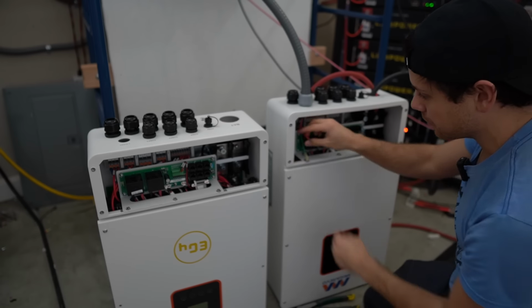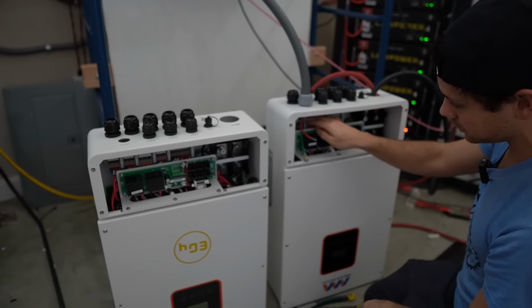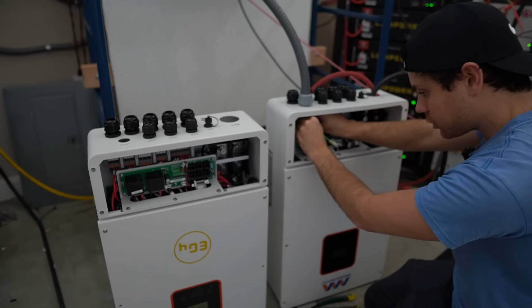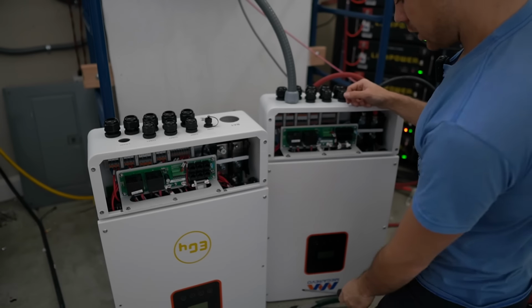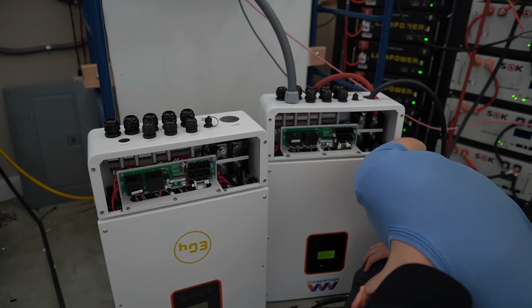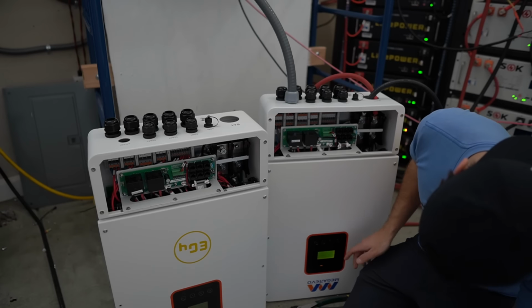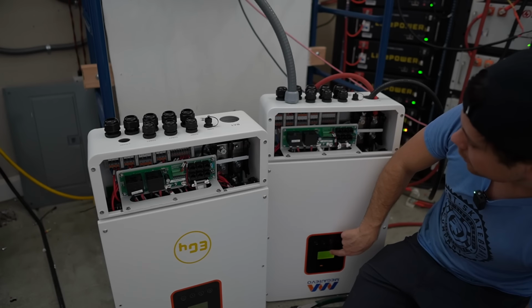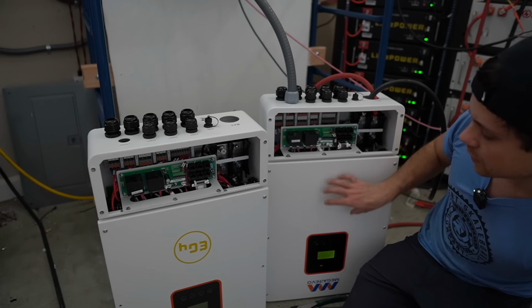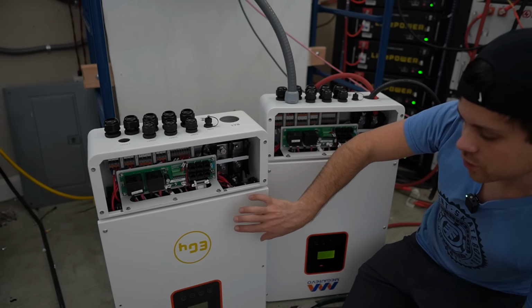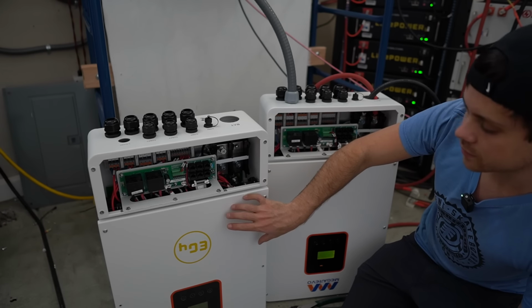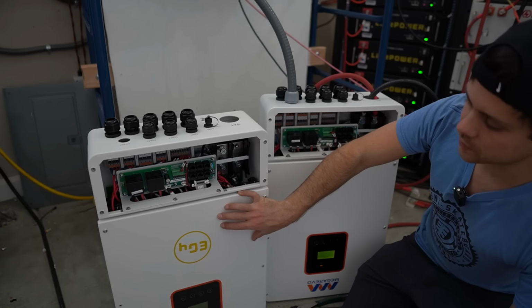I also found out if you push these ferrules into those terminals, it will click right in. Super easy. All right, we should be good to go. Oh no, and it has an error code. It states BMS communication failure, so that means we need to switch the settings to lead acid. The EG4 actually arrives out of the box with lead acid, so this one does not require BMS communication.